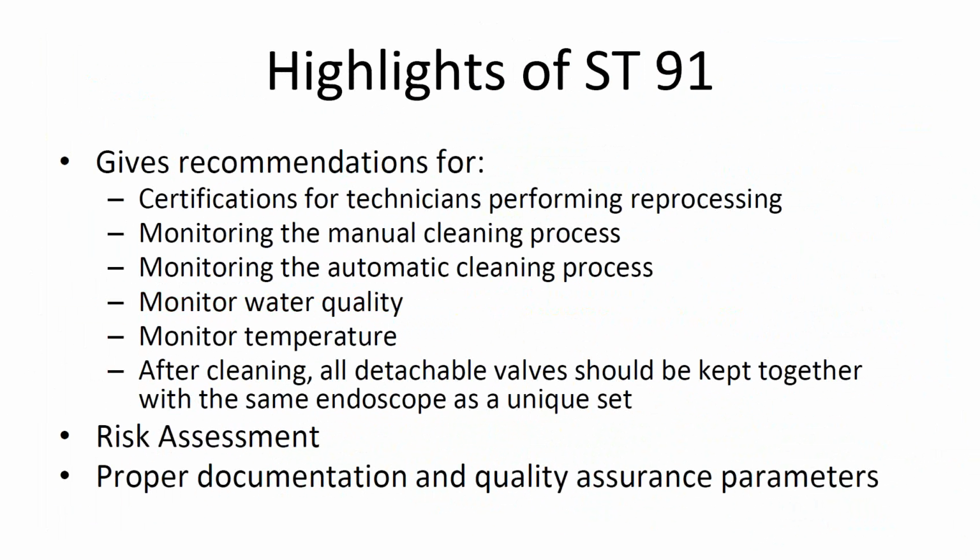And that would help to identify those units very quickly. Another highlight of ST91 is a risk assessment and recommendations for when to do risk assessments, with a large one in there being around how to determine a storage interval or hang time for endoscopes.